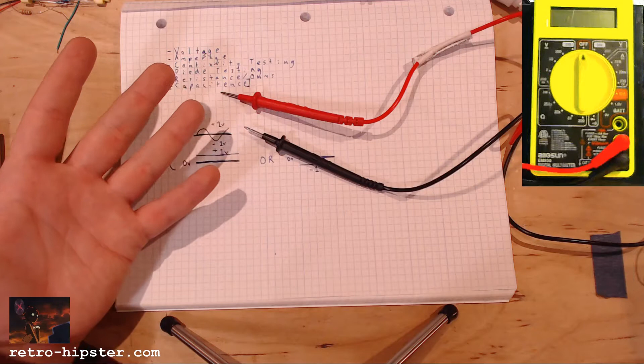So let's measure some voltage. On a manual ranging meter like this, you'll notice it's got different ranges going up and down. This is on the DC range. If we go all the way to the bottom, it says 200M, meaning your circuit should have no more than 200 millivolts to use this range. This 2 means you should have no more than 2 volts to use this range.